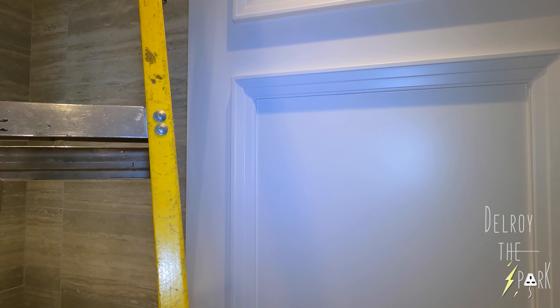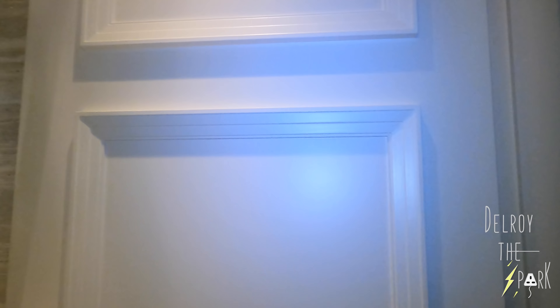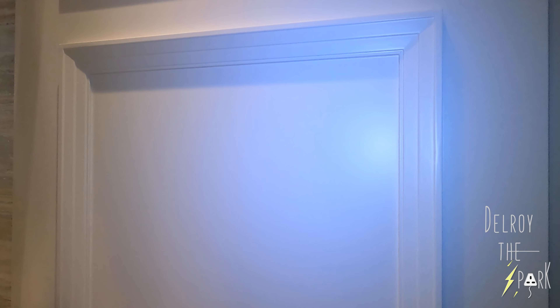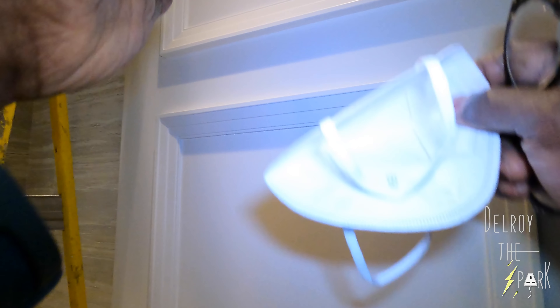After four years — this is a new build property. These fans are good, I don't know why it's burnt out. There's no guarantee that this one isn't going to burn out in three years, because I can't see how it's installed. For all three to happen — I haven't checked the other two yet. When I see a fan on a wall and it's vented outside, I'm happy — I know it's done properly. But when it's in the ceiling and the wall's far away, when I pulled it down I could see it had a pipe on it with flexi duct taped to it. Where that flexi duct goes and how it gets there is another thing. This one's working now — I'll put the cover on and go look at the other two.